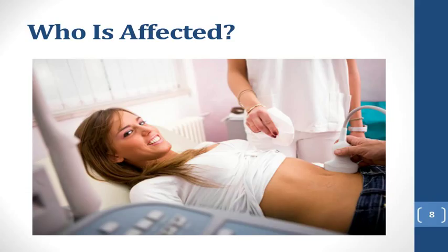Well, she's going to wipe the patient off, but what is she using to wipe the patient off? I know this is very detailed, but this is exactly the type of scenario that medical device manufacturers use to internally identify what problems could be in their device when it's actually used on patients. Because, as I'd mentioned previously, the vast majority of devices out on the market don't have human trials data associated with them. And we will go into some of that in further slides as well.